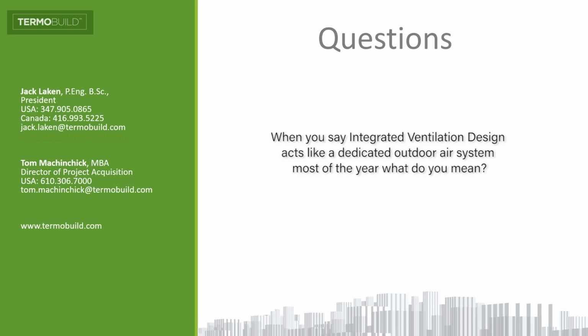Right. That's an interesting point. There are 2 air changes that are required for many buildings according to the American Society for Heating and Refrigeration. That's the ASHRAE ventilation code requirement. And what it means is in 24 hours, the air recirculates 48 times. So that is something that our buildings don't have. In fact, about 30-35% of our buildings operate in 100% fresh air mode without recirculation.